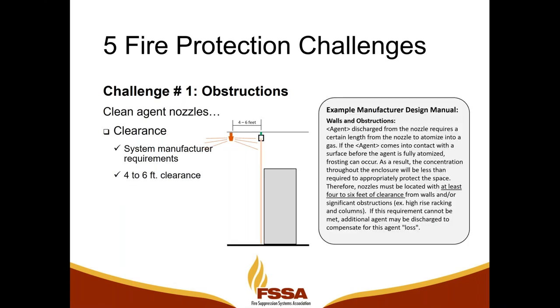Another thing with clean agent systems is the gaseous agent as it comes out of the nozzles. For halocarbon-based systems and the ketones, it's usually a two-phase flow fluid. So it's a combination of both gas and liquid coming out of the nozzle, and it takes usually 4 to 6 feet of clearance for that agent to vaporize and fully become a gas.